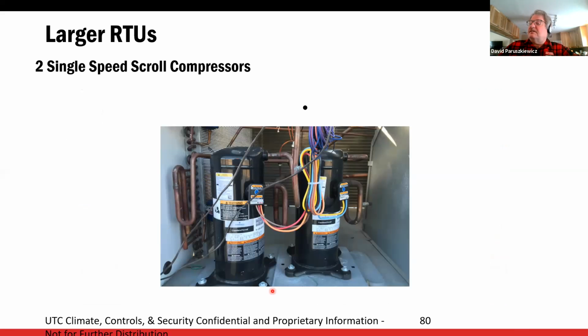All right, the bigger units, once we get above, I think it's 7.5, we're going to jump up to 2 separate single speed scrolls. All right, first stage will always be the lower one. Okay. So on the evaporator, first stage will always be the lower one. Now that's important that we keep an eye on that too, because if stages get screwed up, the condenser fans are connected to stage 1. And I've had this where guys swap stages and now the condenser fans don't come on because they did some wiring change and second stage comes on before first stage.